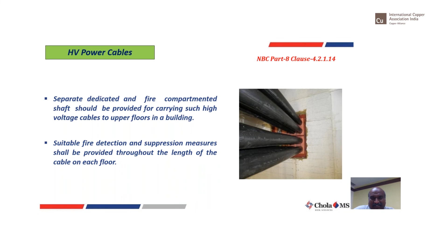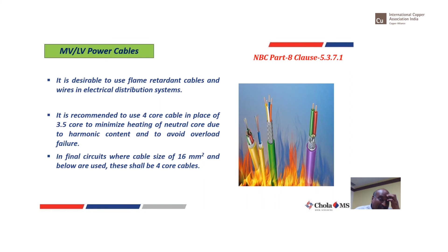This is again, apart from the copper to be used. One more mistake that people make is using the 4-core and 3.5 core. It is always recommended to go with the 4-core cable if you're having a neutral, 3-phase with neutral, because please don't use 3.5 core, which can unnecessarily create heating and harmonic issues in the circuit. Always go with 4-core, and for smaller sizes, less than 16 square mm, use copper.